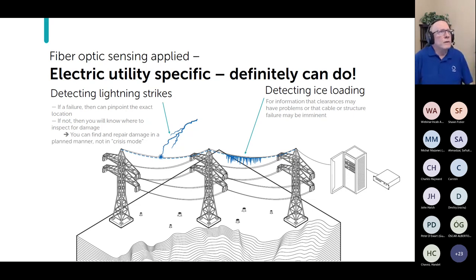Because at least one customer had an instance where the cable got struck by lightning at some point. They didn't know exactly when. And enough of the cable was damaged that it lost a lot of its strength. Then when winter came and there was ice loading, the cable failed mechanically. But the damage had obviously been there for a long time. So this concept of gathering the data will tell you to go look for damage, and then you prevent a crisis like that, right?